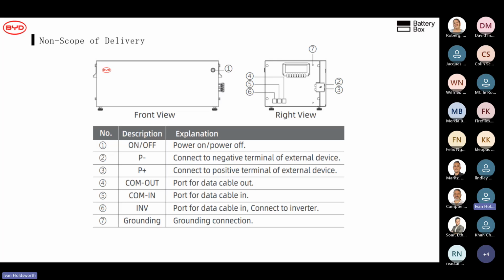And here we can see the right side view. You've got your cable to your inverters on number 6. Generally speaking, it's a straight cable. But for Victron, you've got to make sure that you use a Type A or Type B cable. Well, it's recommended to use a Victron Type A cable. And then on your right side, there are the negative and positive power connections. Please make sure the polarity there is correct. And then number 7 is your grounding connection.